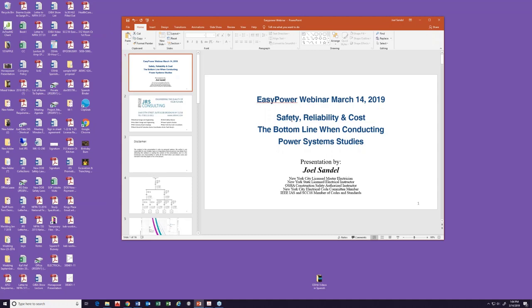For example, in New York City, because we have a high fault current availability because of the strong network that the utility has up here in the condensed areas such as Manhattan and the surrounding areas, most of the industry is always looking for fuses, because fuses are able to interrupt 200 or even 300,000 amps of available fault current. Therefore, it has become kind of an industry standard to go with.